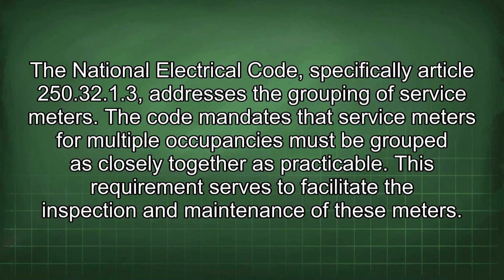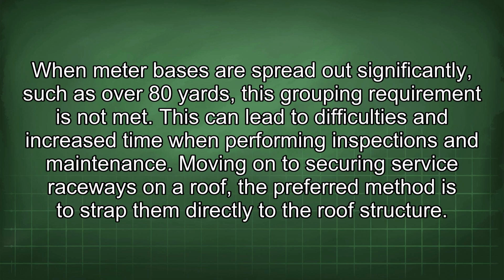The National Electrical Code, specifically Article 250.32.1.3, addresses the grouping of service meters. The code mandates that service meters for multiple occupancies must be grouped as closely together as practicable. This requirement serves to facilitate the inspection and maintenance of these meters. When meter bases are spread out significantly, such as over 80 yards, this grouping requirement is not met. This can lead to difficulties and increased time when performing inspections and maintenance.